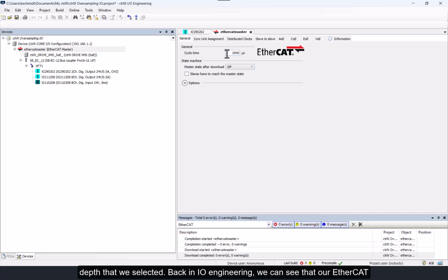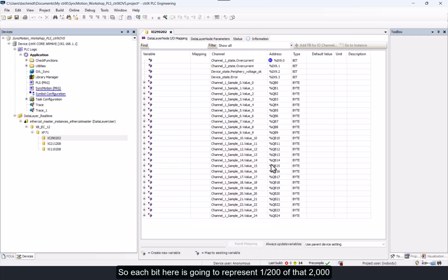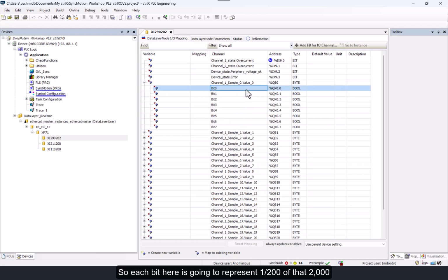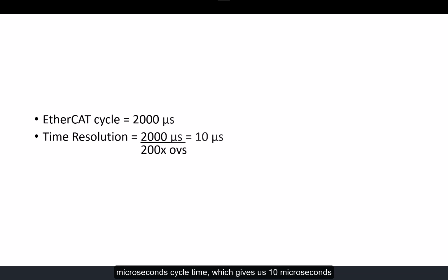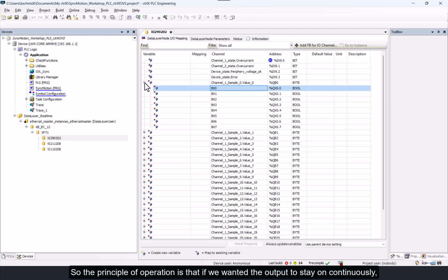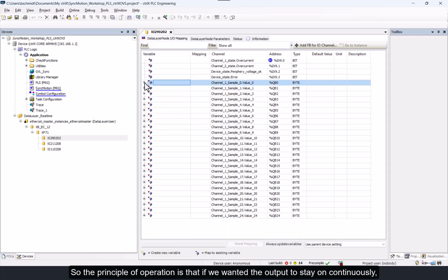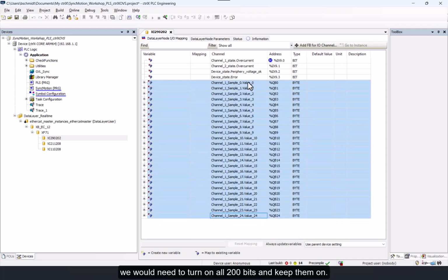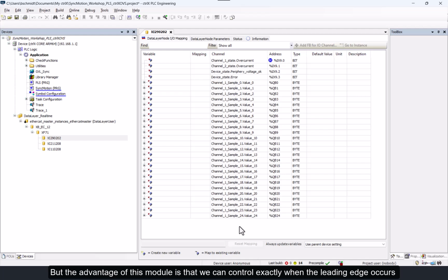Back in I/O Engineering, we can see that our EtherCAT cycle time is set to 2 milliseconds, or 2000 microseconds. So each bit here is going to represent 1/200th of that 2000 microsecond cycle time, which gives us 10 microseconds per time slice that we can control with these bits. So the principle of operation is that if we wanted the output to stay on continuously, we would need to turn on all 200 bits and keep them on. But the advantage of this module is that we can control exactly when the leading edge occurs within the EtherCAT cycle by turning on only a portion of these bits during the first PLC scan.